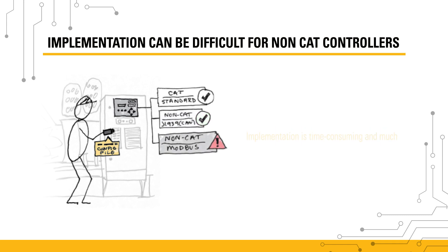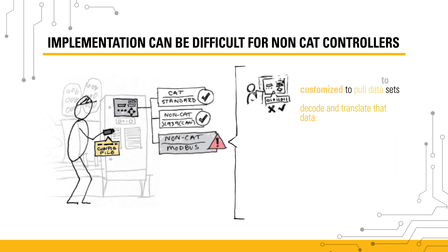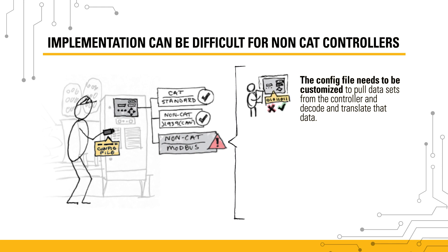But for non-CAT controllers that don't use the standard communication method, implementation is time-consuming and much more difficult. Additional steps must be added to the implementation process. The configuration file must be customized. Non-CAT controllers with unique protocols format and store data differently, depending on the controller's brand, model, firmware, etc. Because of this variation, the standard config file won't work, so a customized config file to decode the controller's data must be built from scratch.